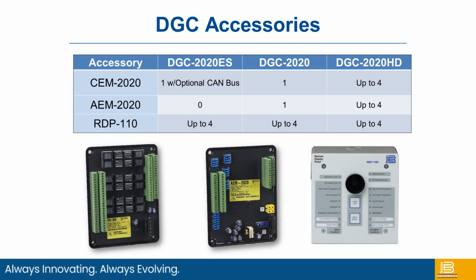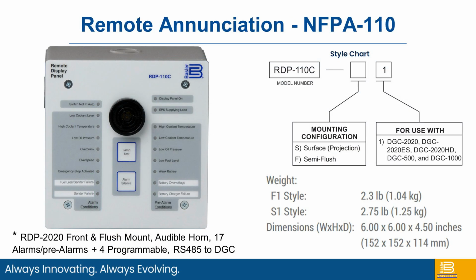Again, I've got a chart here, but as we talk about the HD, you can see that it's extremely flexible and expandable. So this contact module we'll talk about in a minute, analog module, and then the remote display module, and you can have up to 4 each of those. So up to 12 accessories on one DGC-HD. The remote annunciator is utilized for NFPA 110. So it has both an audible horn and 17 programmable LEDs. And it's an RS-485 connection. Again, there's a style chart to help you understand how to order.